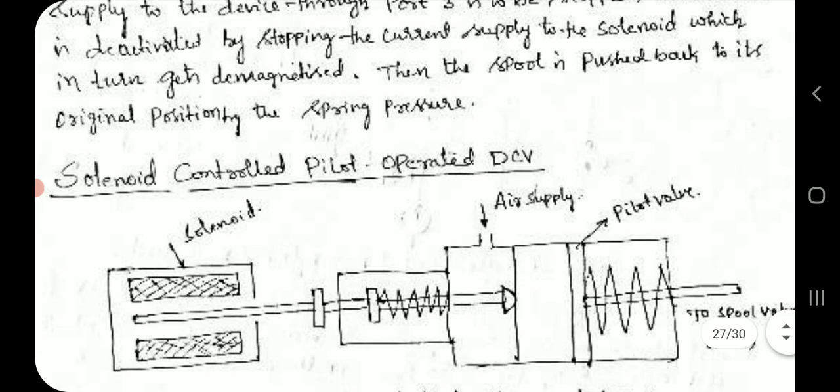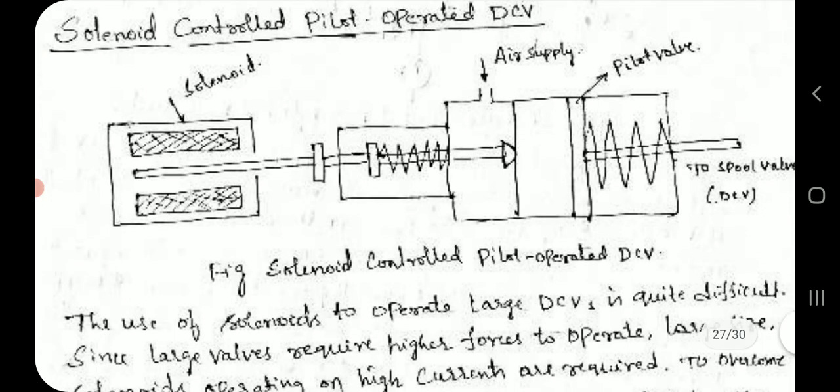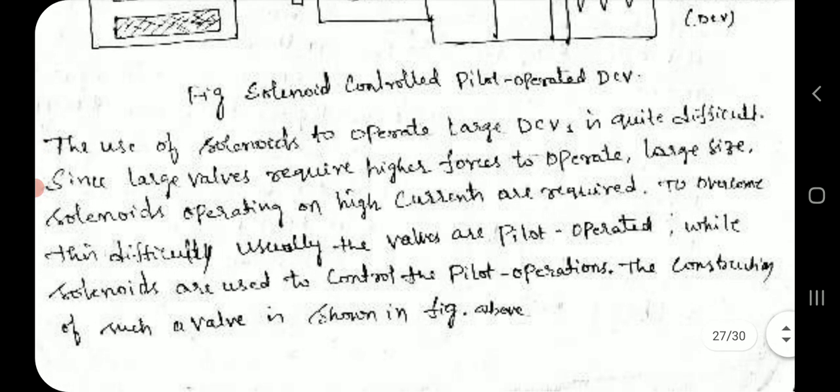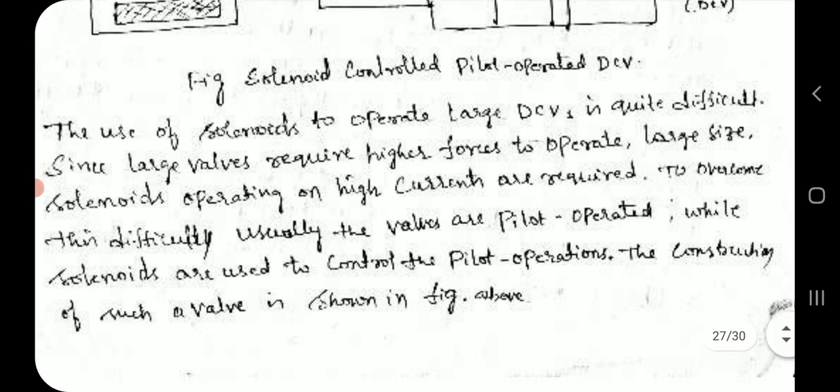Solenoid Controlled Pilot Operated Direction Control Valve. The use of solenoids to operate large direction control valves is quite difficult, since large valves require higher forces to operate. Large size solenoids operating on high currents are required. To overcome this difficulty, usually the valves are pilot operated while solenoids are used to control the pilot operations.